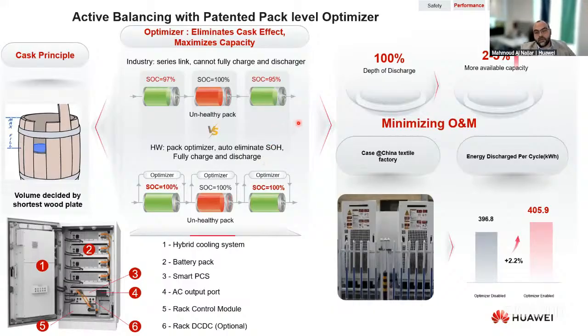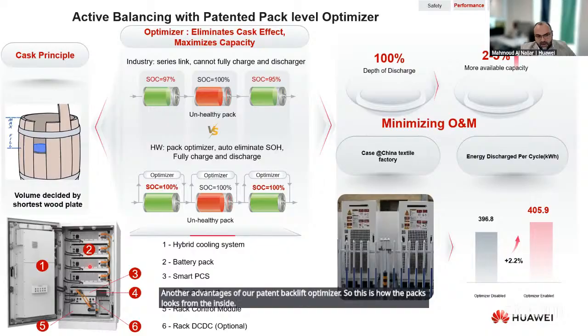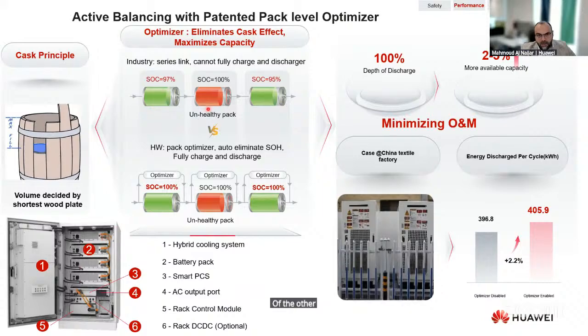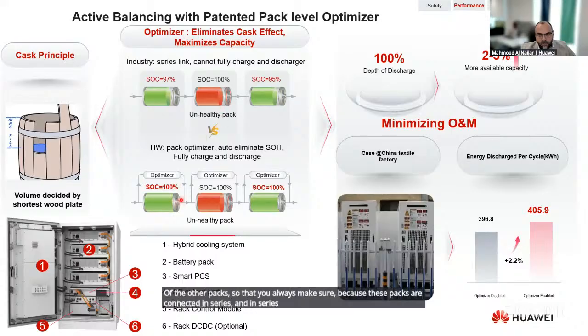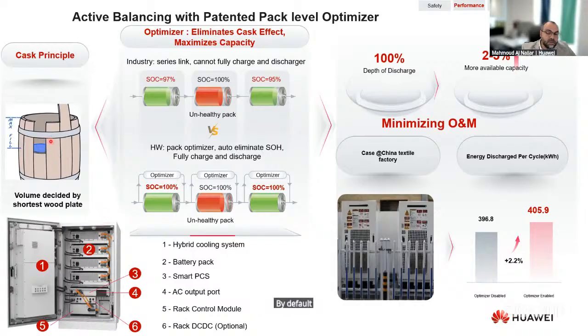Another advantage is our patented pack level optimizer. So this is how the packs look from the inside. Inside each battery pack, you will find a pack level optimizer to make sure each pack can charge and discharge independently of the other packs. Because these packs are connected in series, in series you will always get the lowest current. So if one pack is having less output, without optimizers you would definitely by default get less energy being charged and discharged from the batteries.